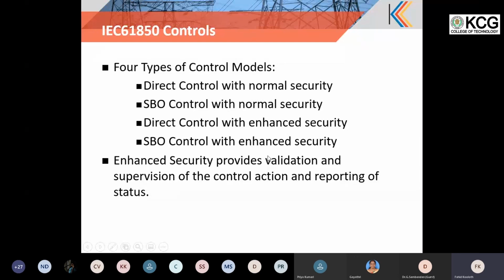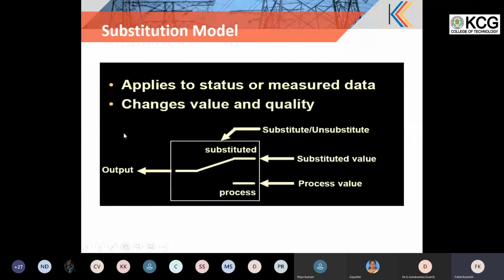Then, as I mentioned, there is a model named the substitution model also. If a process parameter has gone faulty, or a transducer is faulty and you are receiving a faulty value every time, and your operation keeps getting a problem, then what you can do is substitute a pre-configured ideal value. Once substitute is enabled, the substituted value will be received as output. And if unsubstitute is enabled, this switch will go to the process side and you will get the process value as output.